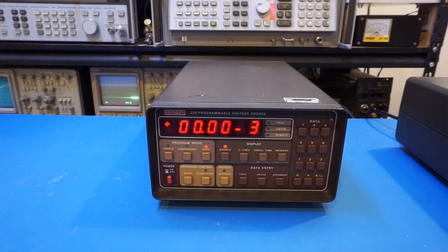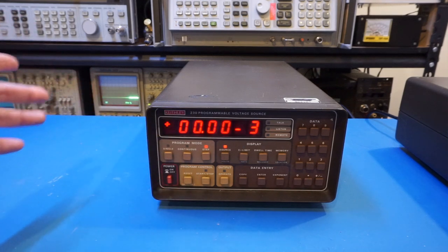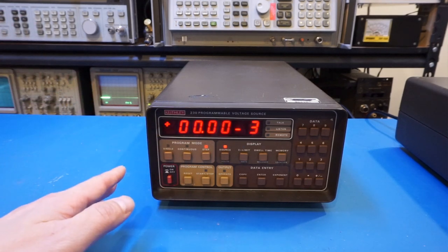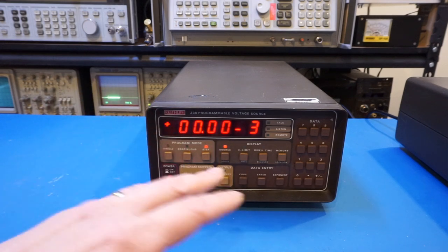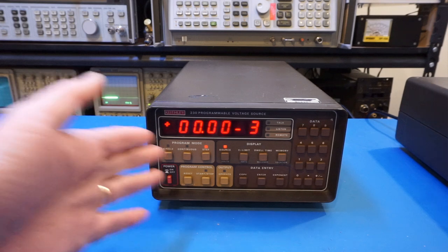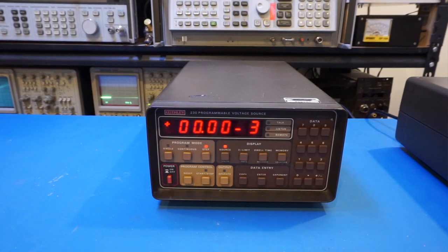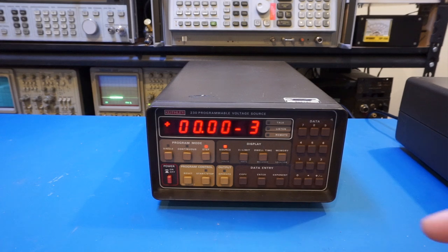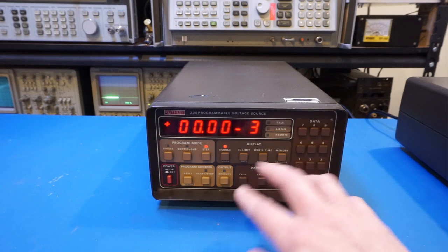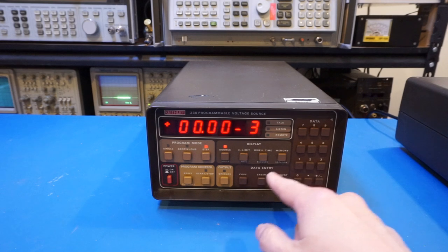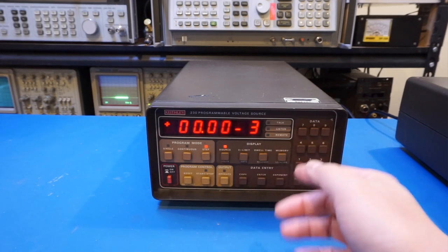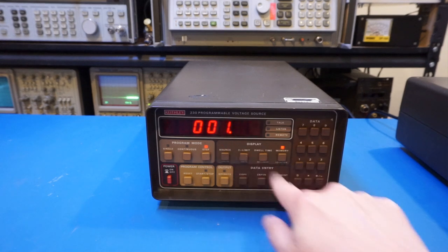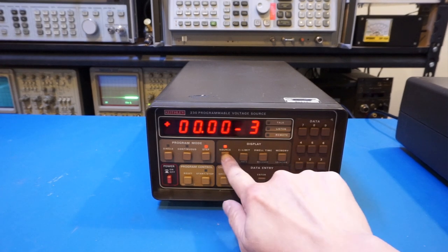And here's the setup. The output from this Keithley 230 is hooked up to that Tektronix 2465 so that when we program a set of voltages through different channels and play them back continuously, we can observe a waveform on that oscilloscope. The first waveform I'm going to build here is a very simple one, just simply a pulse. And for that, I'm going to utilize two memory channels. The first one I'm going to set to zero, which by power on is a default. So now you can see that we're on memory channel one.